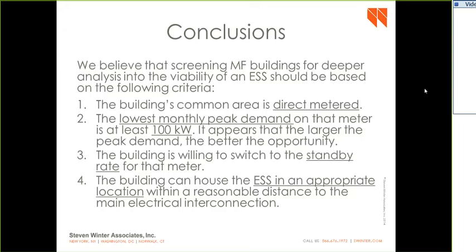Looking at all the different rates for each building, the best one in every case was the standby rate, allowing that daily as-used demand charge, so you're not hit with a charge for the single day you used the most electricity in a given month. The last point, somewhat obvious, is that you need an appropriate location to house the system, but they've been fairly flexible about where you can actually house it.